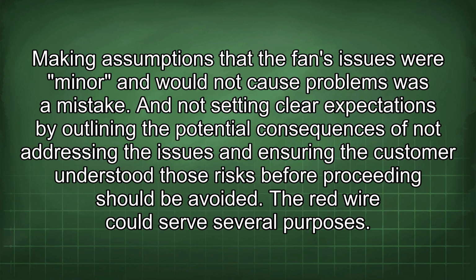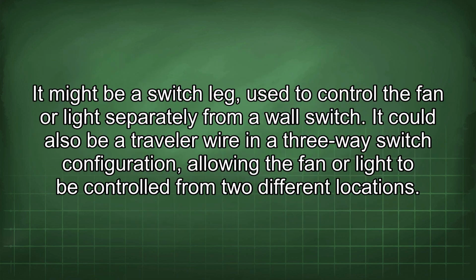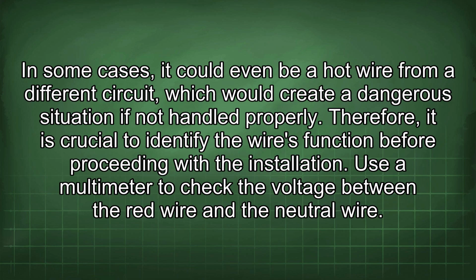The red wire could serve several purposes. It might be a switch leg used to control the fan or light separately from a wall switch. It could also be a traveler wire in a three-way switch configuration, allowing the fan or light to be controlled from two different locations. In some cases, it could even be a hot wire from a different circuit, which would create a dangerous situation if not handled properly. Therefore, it is crucial to identify the wire's function before proceeding with the installation.